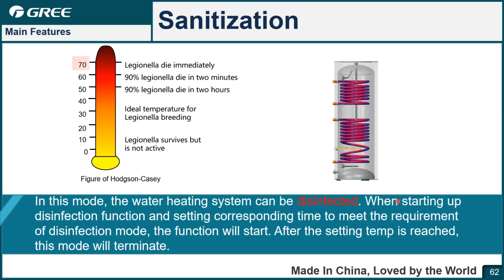For the water tank, because of the water quality and the running time, maybe some bacteria or some dirt inside. So actually the unit can use the disinfection function to heat the water to around 70 degrees Celsius to kill the bacteria inside, to keep the water clean and healthy.